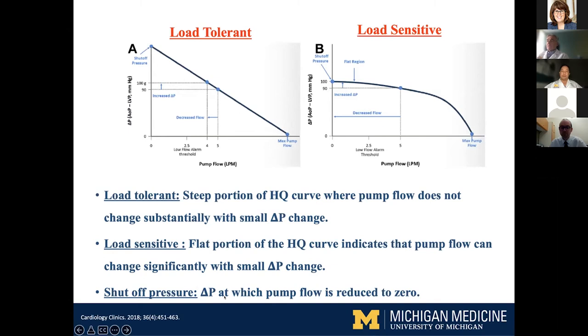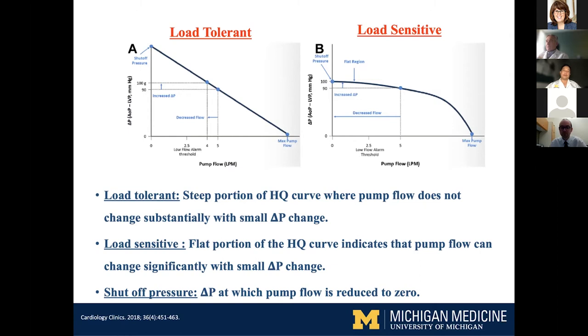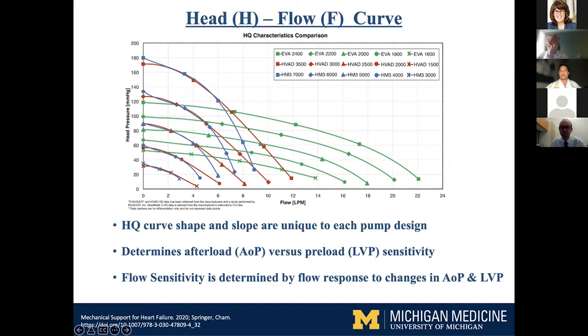There's also a shutoff pressure — the head pressure, or delta P across the pump, can go to zero. The head pressure is aortic pressure minus LV pressure, so if aortic pressure is very high and that difference becomes very large, you don't get any flow. An extreme example: if you pinch off the outflow graft, aortic pressure is effectively infinite and you get no flow, though the pump can still rotate at a certain speed. Similarly, if preload is so low that there's no blood, you won't get any flow. Different pump designs have different versions of these curves.